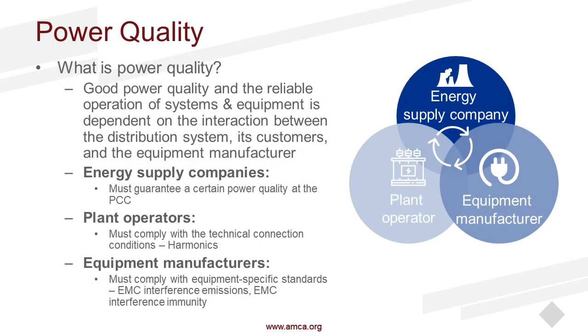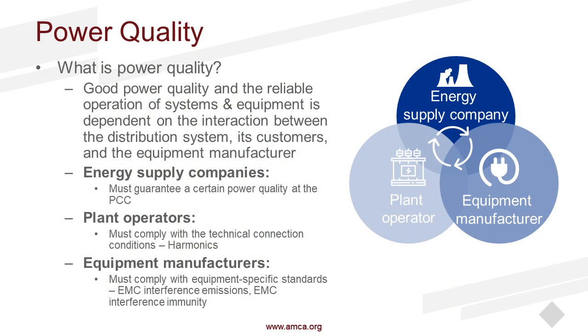So on the energy supply company side, they want to make sure that their power coming to the point of common coupling is of good quality. The plant operators want to follow protocols, regulations, and standards to make sure that they are meeting requirements. This is reducing harmonics, which we'll talk about later. And then on the equipment manufacturer side, they also want to make sure that their products are helping to keep that power quality in good working condition. So things such as EMC interference emissions, EMC interference immunity. And so this relationship is where you're getting your power quality, and each can affect each other.